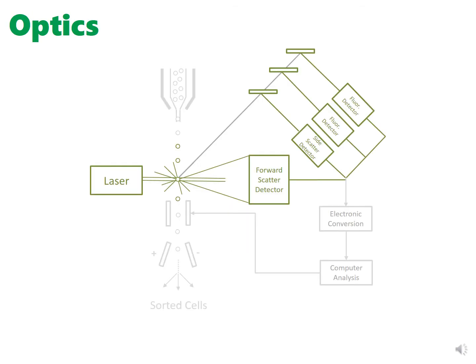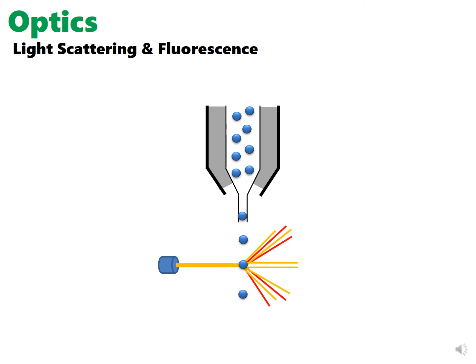The optics involves the light applied to the sample, as well as a combination of mirrors and detectors. When the laser reaches each cell, at what is called the interrogation point, the light is scattered and fluorescence is also emitted in the presence of fluorophores.